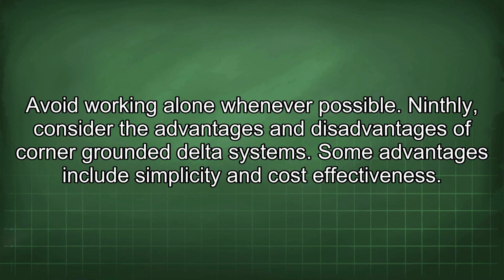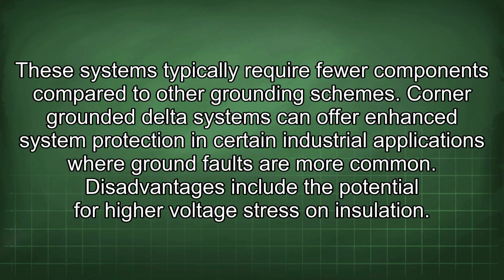Ninthly, consider the advantages and disadvantages of corner-grounded delta systems. Some advantages include simplicity and cost-effectiveness. These systems typically require fewer components compared to other grounding schemes. Corner-grounded delta systems can offer enhanced system protection in certain industrial applications where ground faults are more common.